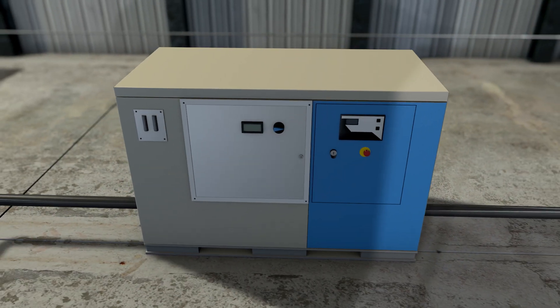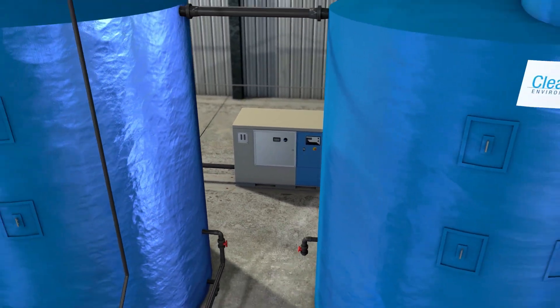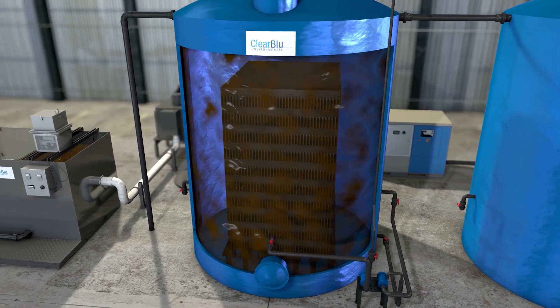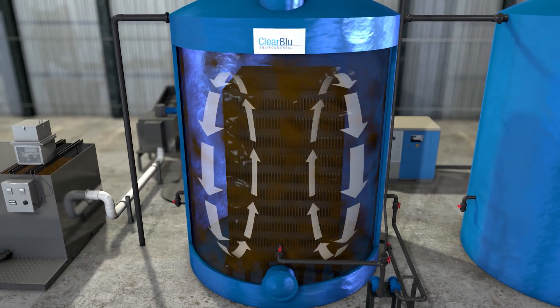The next stage is our unique continuous flow updraft aerobic digestion utilizing nano-bubble technology. Wastewater is circulated through a dense media pack with a volume-multiplying mixing system — this is the ClearBlu updraft biodigester system. The bacteria are 60% more efficient because they have thousands of square feet of fixed film surface with this molded polypropylene honeycomb media.